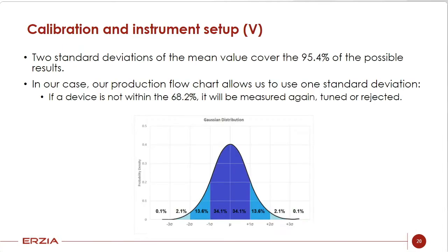Two standard deviations of the mean value covers 95.4% of the possible results. In our case, our production flowcharts allow us to use only one standard deviation. If our device is not within the 68.2%, it will be measured again to check that our case is in the corners of the Gaussian distribution and it is not the mean value. If we have to test it again, we will do it. If we have to calibrate again, we will also do it. If the result is confirmed that the mean value is close to our result, and it is not a problem of the distribution, we will tune this device. And finally, if there is nothing we can do, we will reject it.